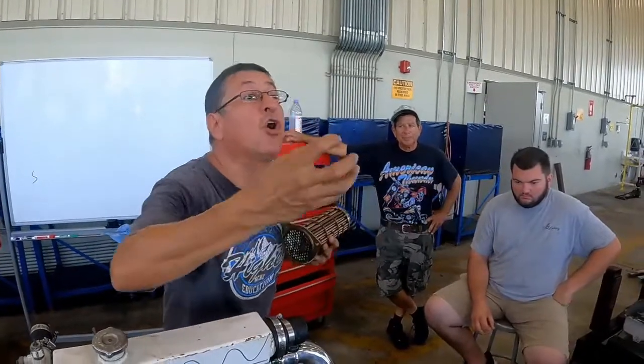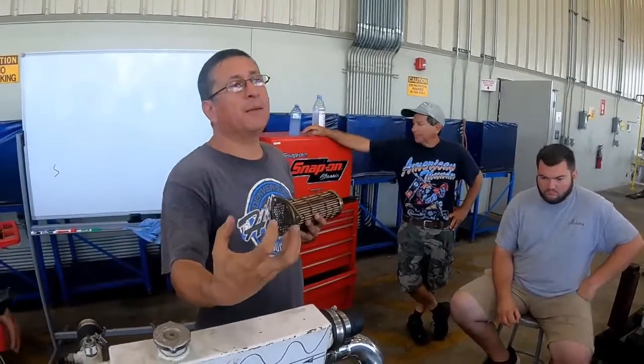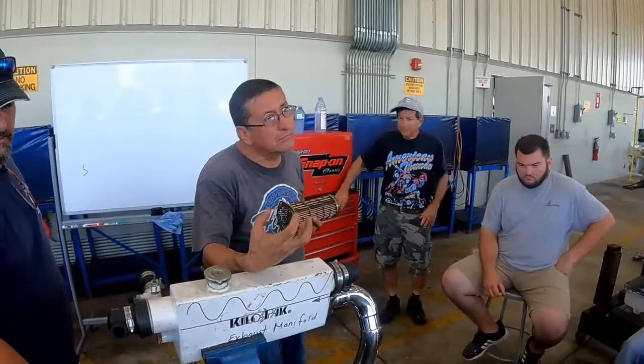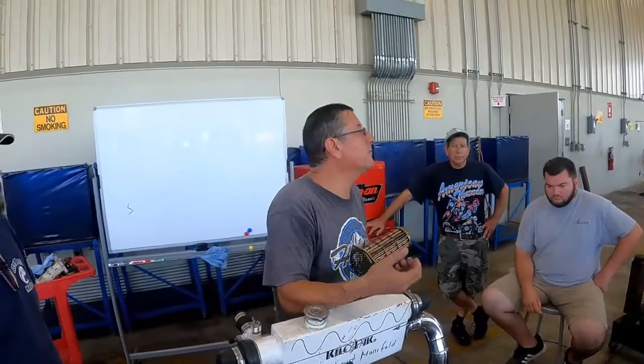I have a sample of oil, Roberto, and in the sample I found too much calcium and too much sodium, which is salt water mixed in. In the sample, too much nickel means the oil cooler. I have a fuel sample. Yeah, you can take fuel samples. And I have a lot of nickel in the fuel sample. Same problem: the heat exchanger for fuel.